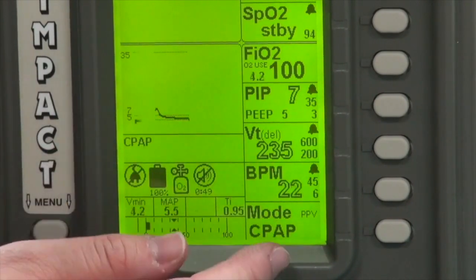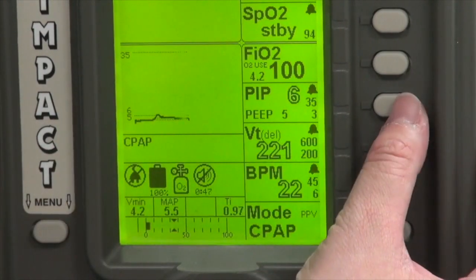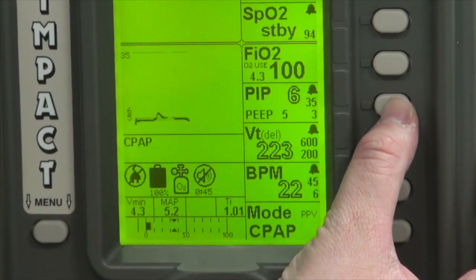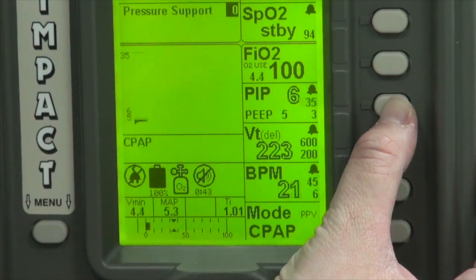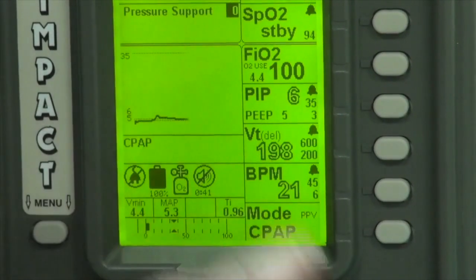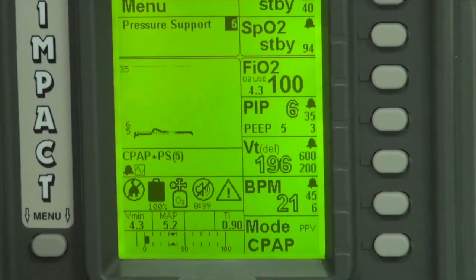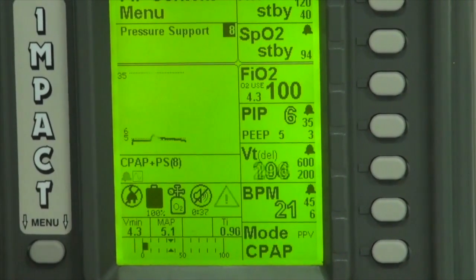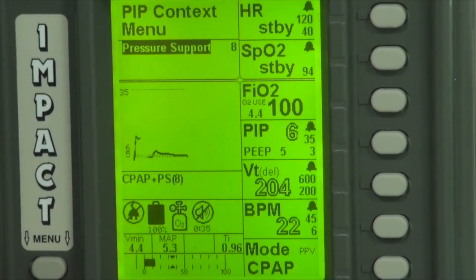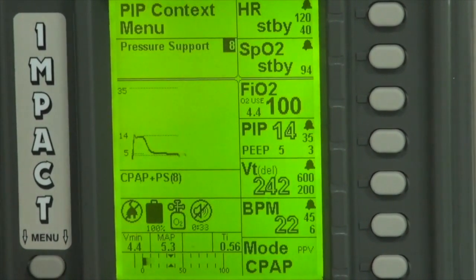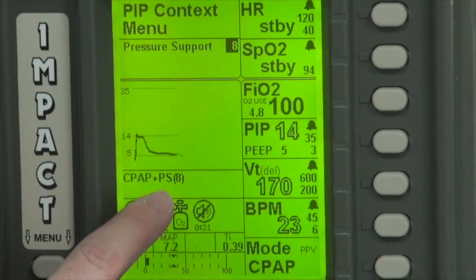In order to set our pressure support, we need to press and hold the button next to the pressure rectangle. You see over here, pressure support comes up. Adjust with the wheel to what we need. 8, for example, and confirm. You will see pressure support of 8 come up over here.